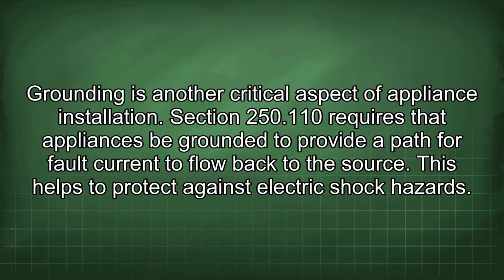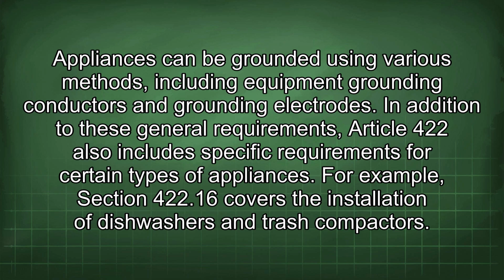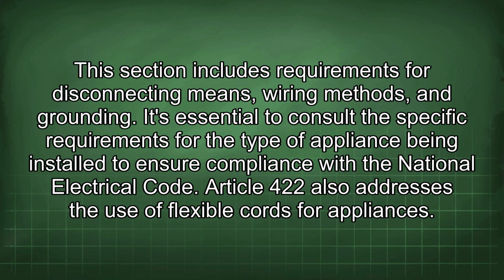Grounding is another critical aspect of appliance installation. Section 250.110 requires that appliances be grounded to provide a path for fault current to flow back to the source. This helps to protect against electric shock hazards. Appliances can be grounded using various methods, including equipment grounding conductors and grounding electrodes. In addition to these general requirements, Article 422 also includes specific requirements for certain types of appliances. For example, Section 422.16 covers the installation of dishwashers and trash compactors. This section includes requirements for disconnecting means, wiring methods, and grounding.